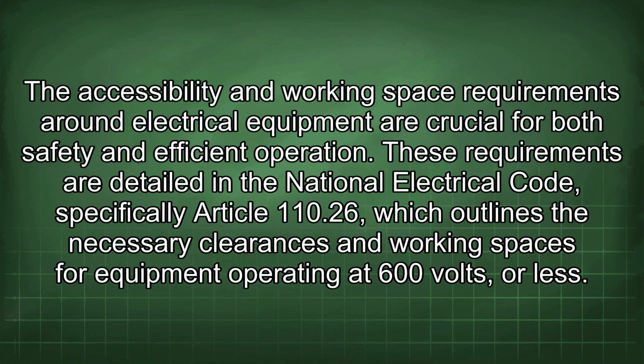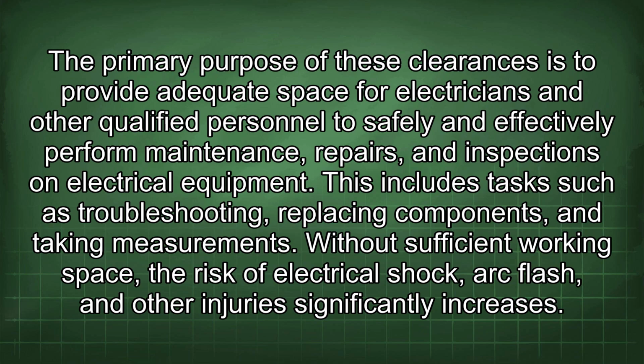The accessibility and working space requirements around electrical equipment are crucial for both safety and efficient operation. These requirements are detailed in the National Electrical Code, specifically Article 110.26, which outlines the necessary clearances and working spaces for equipment operating at 600 volts or less. The primary purpose of these clearances is to provide adequate space for electricians and other qualified personnel to safely and effectively perform maintenance, repairs, and inspections on electrical equipment. This includes tasks such as troubleshooting, replacing components, and taking measurements. Without sufficient working space, the risk of electrical shock, arc flash, and other injuries significantly increases.